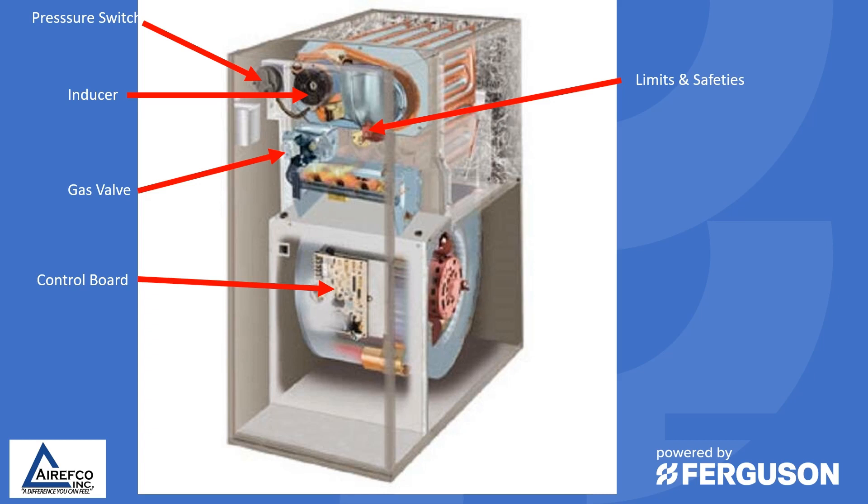Limits and safeties are seen by homeowners and some technicians as a nuisance, but these switches and safeties are designed to protect the furnace and the people that reside in the home. Whenever limits and safeties are tripping, there usually is a problem that you need to investigate, find out why it's happening, and fix it. The burner section needs to be observed when the furnace is operating to make sure you have a clean blue flame and that the flames are going down the tubes of the heat exchanger properly. Any kind of rollout or feathering flames could indicate a problem with the induced draft motor or the heat exchanger itself.